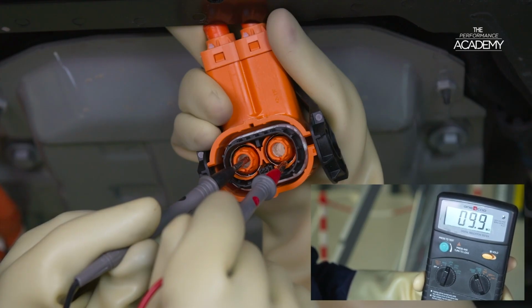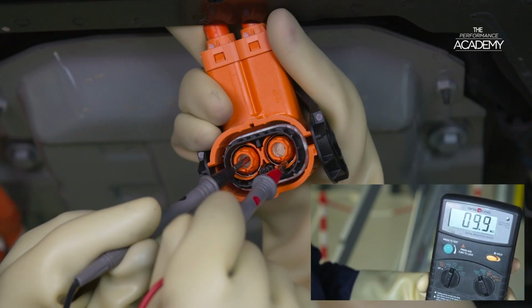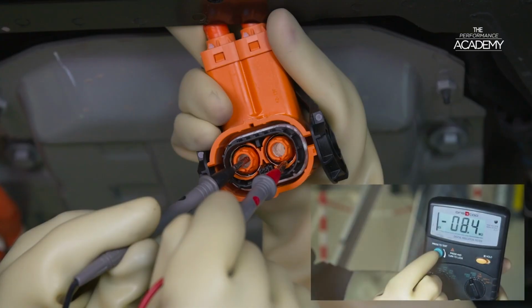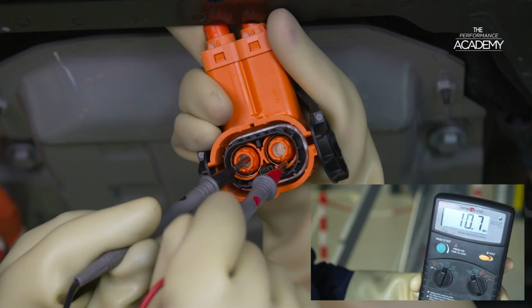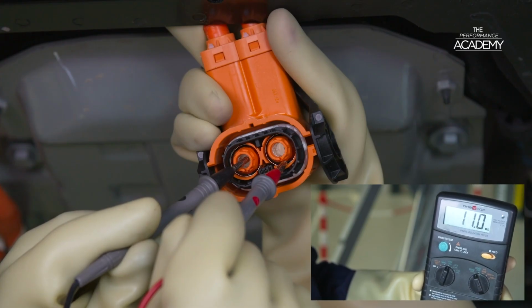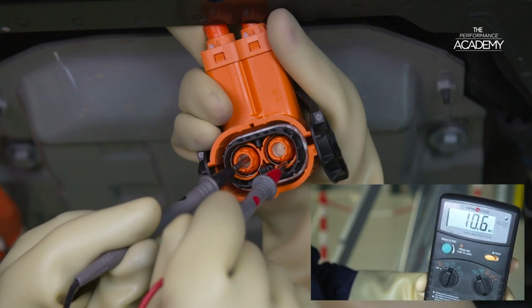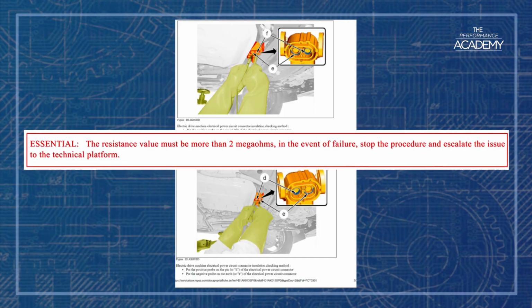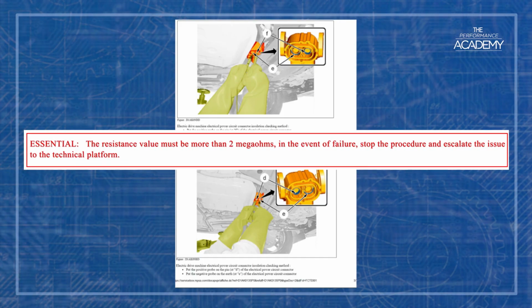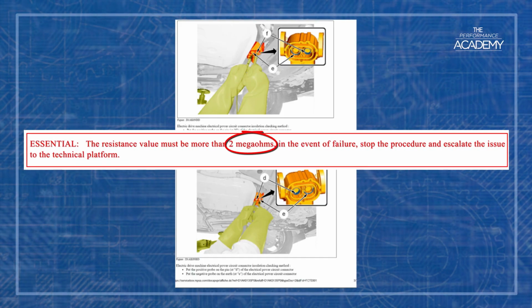Check the resistance value is higher than 2 megaohms. As we run the test, we can see the resistance reading starts at around 6 to 7 megaohms and climbs up and fluctuates at around 10 megaohms, but it's always going up and is well above the minimum threshold reading given in service box of 2 megaohms.